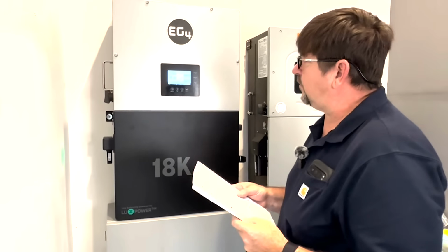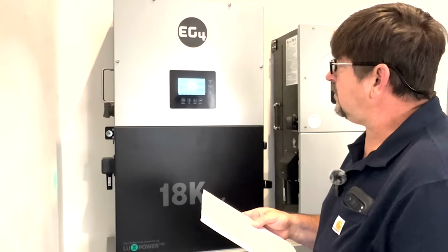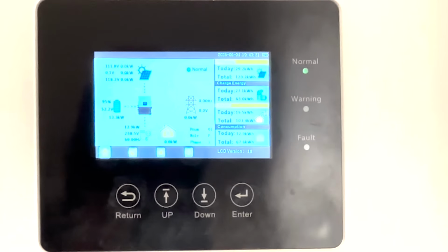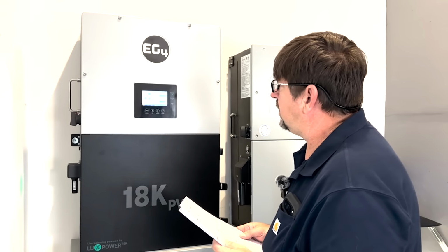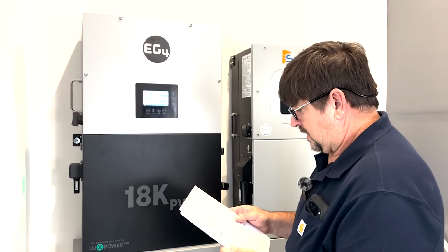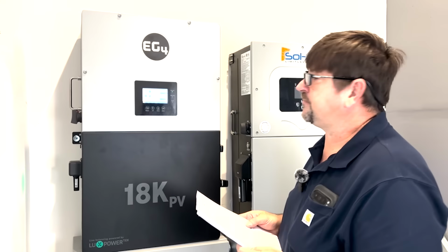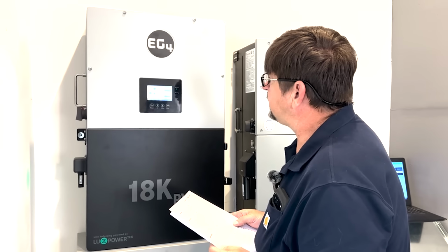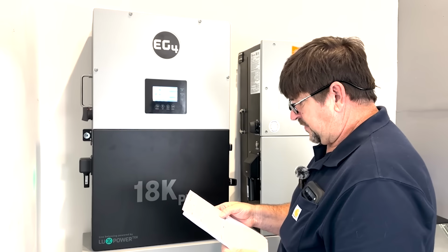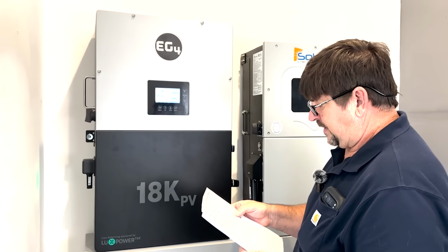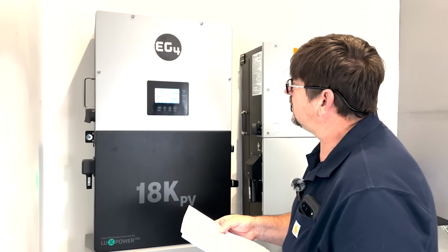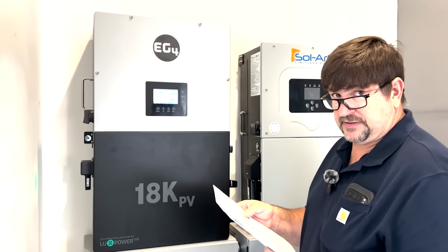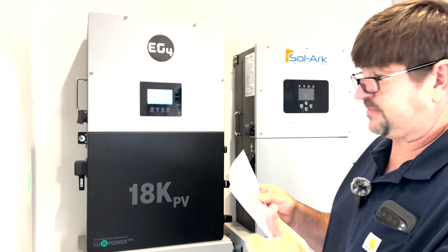Our battery was full when we started our test, so we're just running on battery. We're running a 12.9 kilowatt load. Let's load up beyond the 12.9 and get it closer to the spec sheet. Okay, yeah, we're at 13.6, so you're getting a 13.5. It should run without PV for 10 minutes at this load, or right at what the spec sheet specifies for the 10 minute. That's perfect.